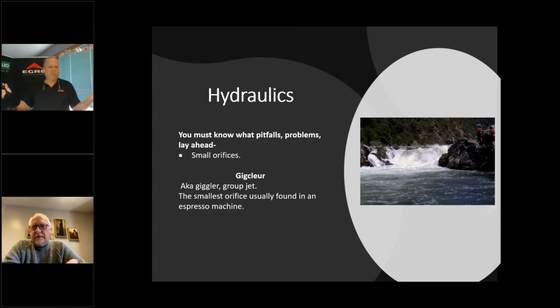All they do is aerospace drilling with water. You know, enough pressure, and it is one of the cleanest cuts that you can get. And so, sorry, I'm remembering when somebody pulled the trigger on a pressure washer, and my hand was in front of it. It drilled real good. But my point being, that giggler is the smallest orifice in the machine, and we're trying to hold back the pressure and then slowly let it fill the top of the puck, and then slowly perfuse down through the puck. And so the problem is it's the smallest jet in the machine.